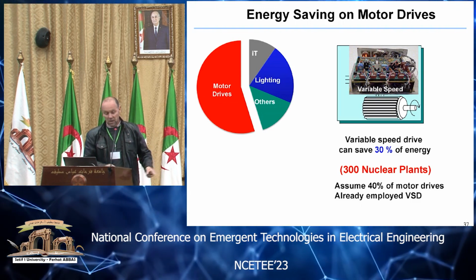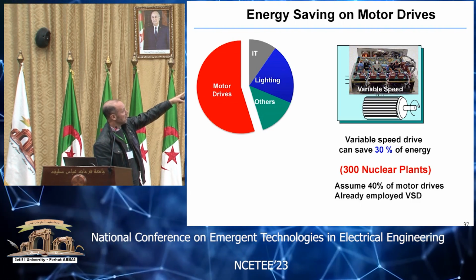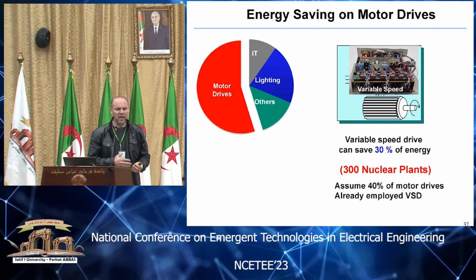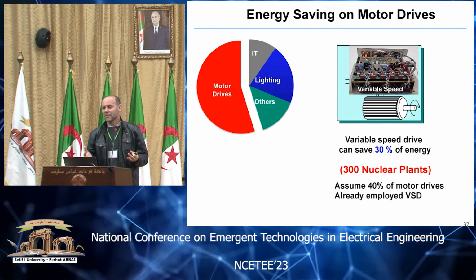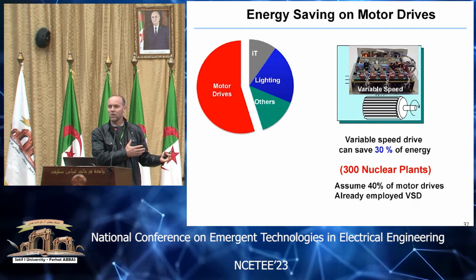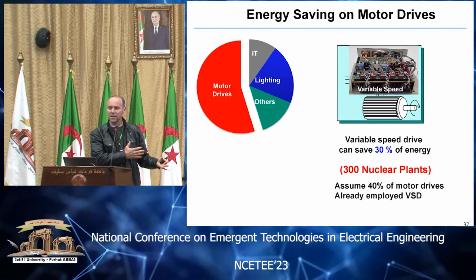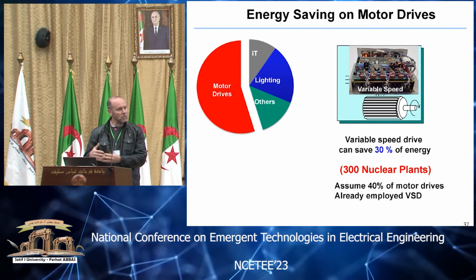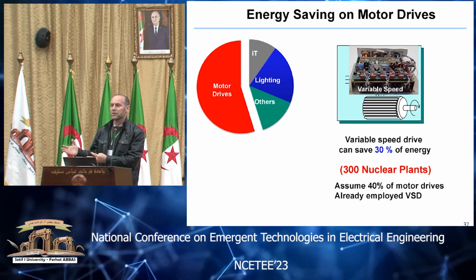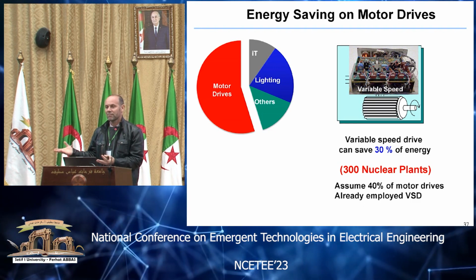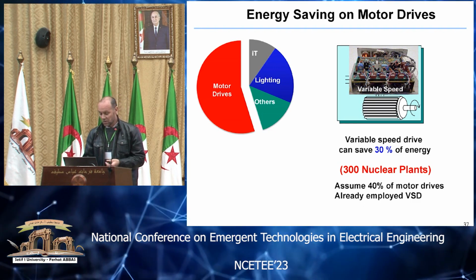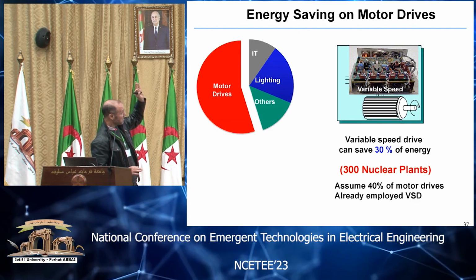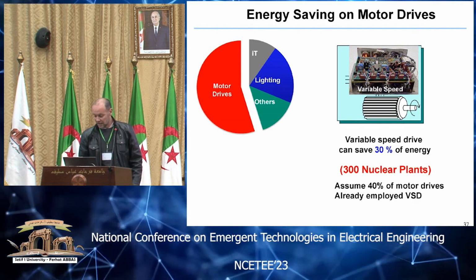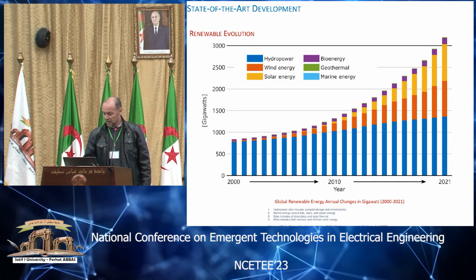So that's about 300 nuclear power plants worth of savings. And what is this VSD? It's a rectifier and inverter. You have a fixed voltage, fixed frequency input, you put it inside the VFD, and it generates a variable voltage, variable frequency output. It's power electronics, and there's a lot of saving in these motor drives.